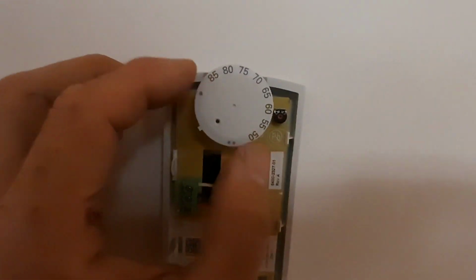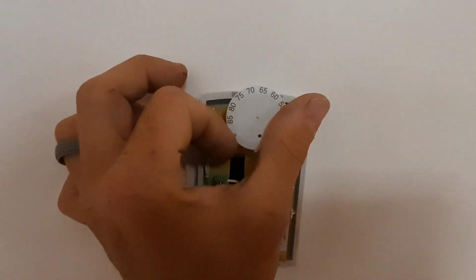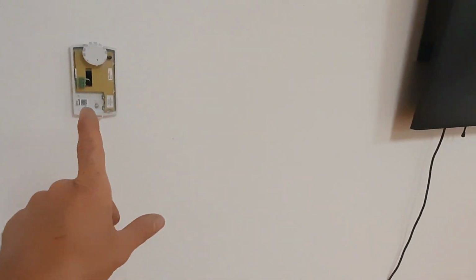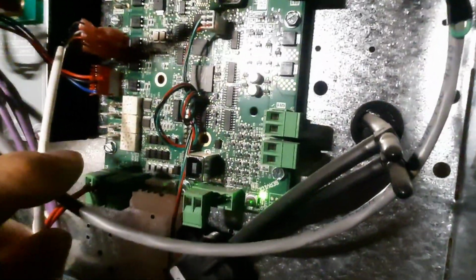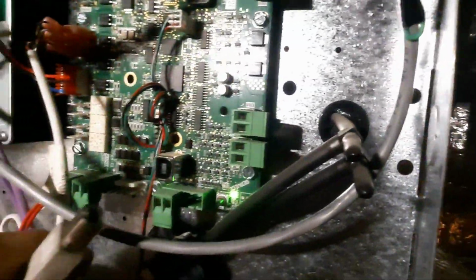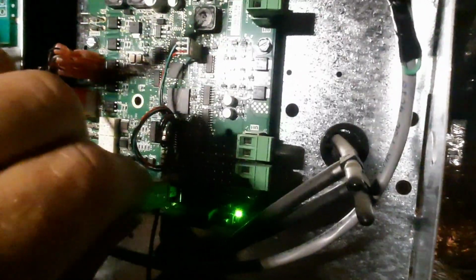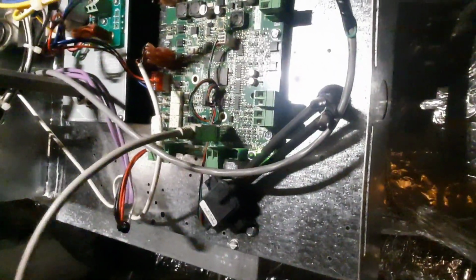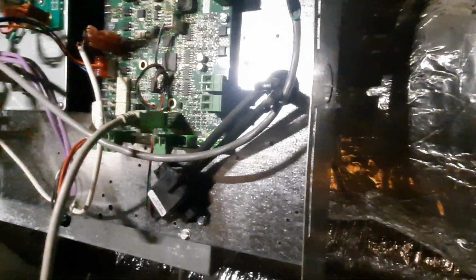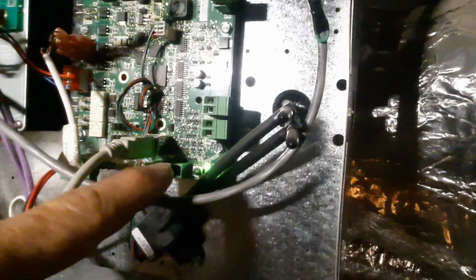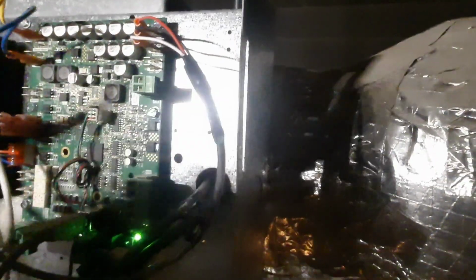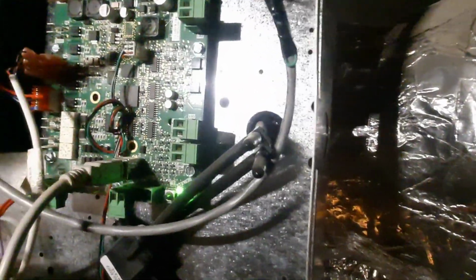Now we've got a thumb wheel. We should be reading the temperature. Let's get the cover on it and plug in and see what we got. So we're going to plug in right here. Now I could go back to the SC main controller and plug in as well, but for this we're just going to plug directly into this unit. And I don't know if you noticed earlier, I had a red flashy light. That's because I didn't have a thermostat connected, so it was sensing there was a problem. Now that my thermostat's connected, that went away. We got a steady green light.